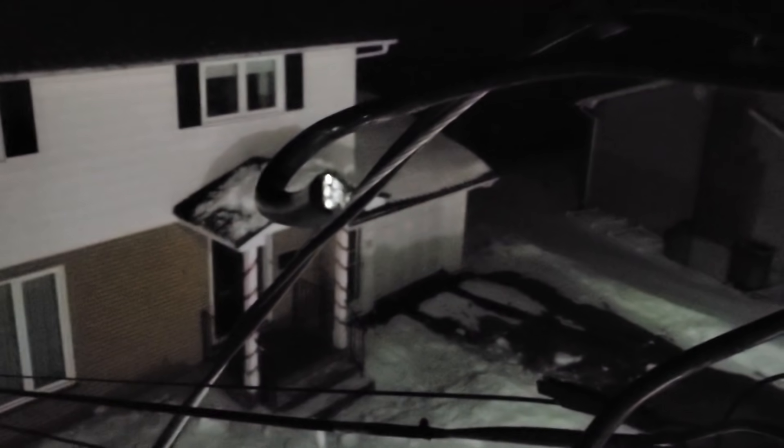We've got both those leads cut now. There's no need to tape the end of the neutral this time — now that both hots are cut, the neutral is still intact. We also unwound the triplex from that neutral, so when we go to hook it back up there's going to be a lot more room to work with, especially with the telephone being this close up at the pole.